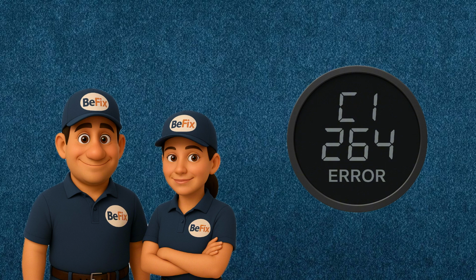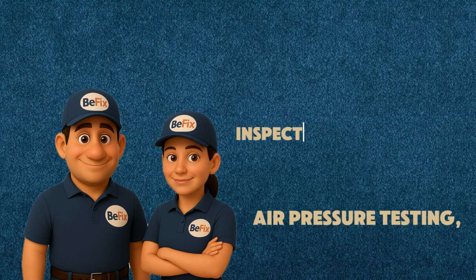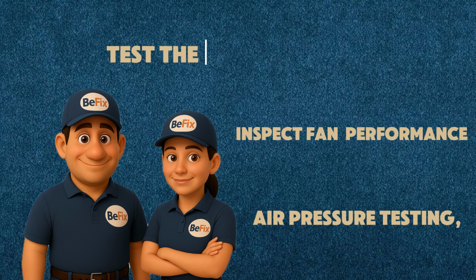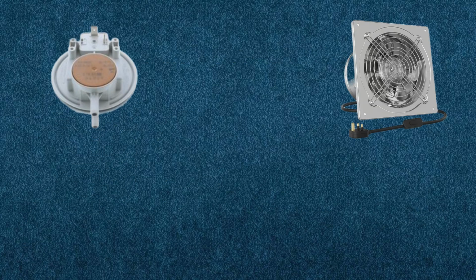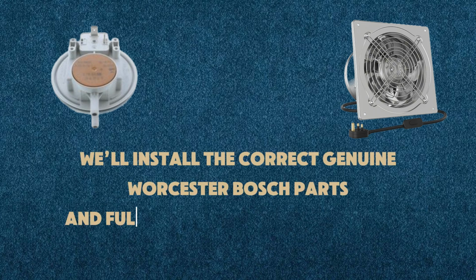If the C1264 error persists, BeFix engineers can carry out air pressure testing, inspect fan performance, and test the switch for continuity. If the air pressure switch or fan needs replacing, we'll install the correct genuine Worcester Bosch parts and fully safety check your system.